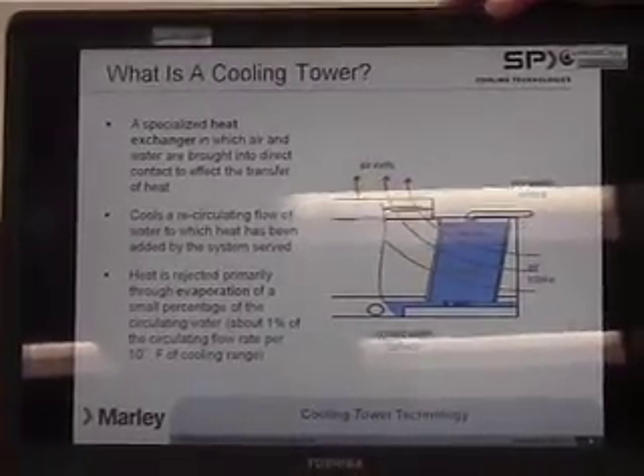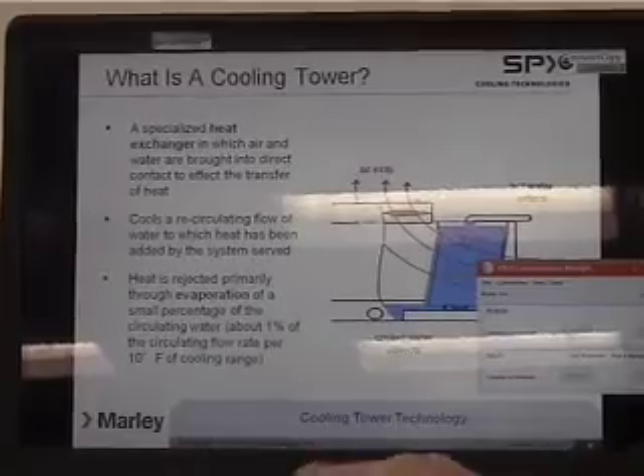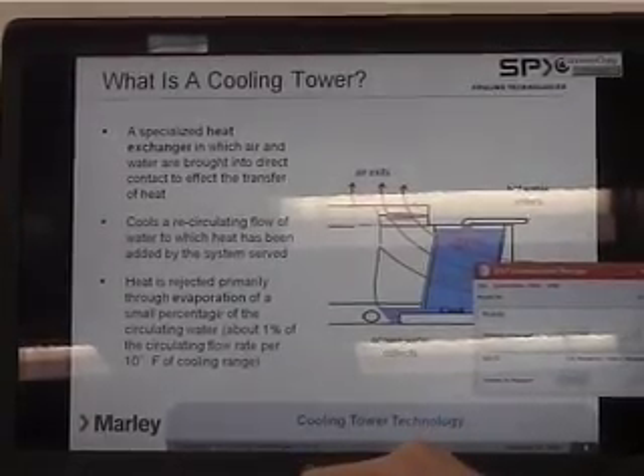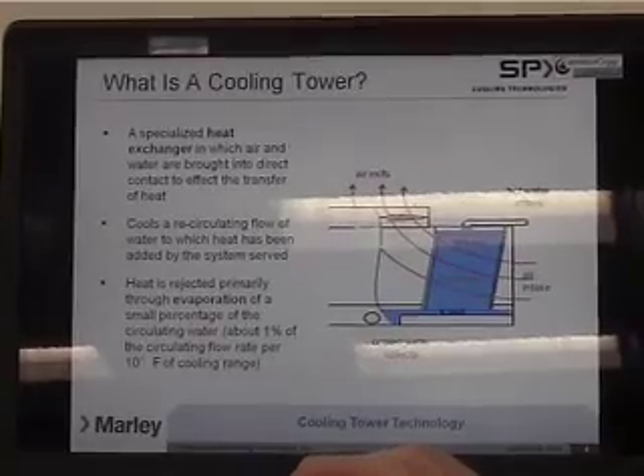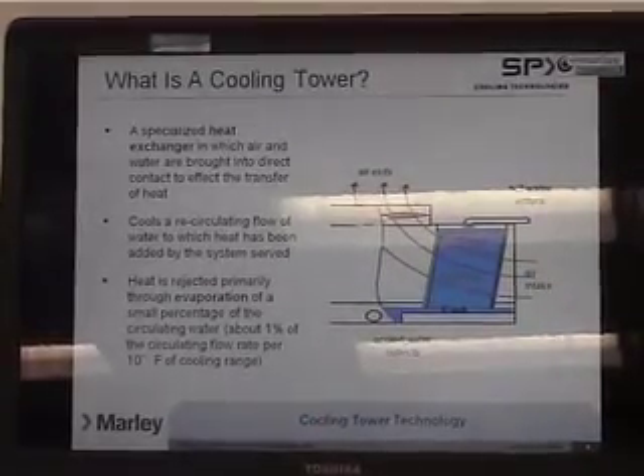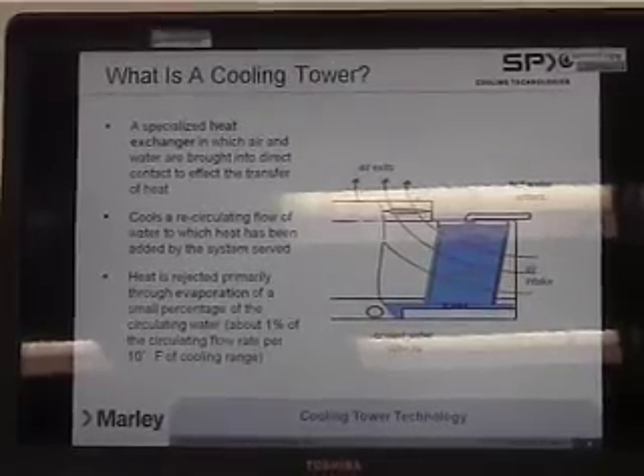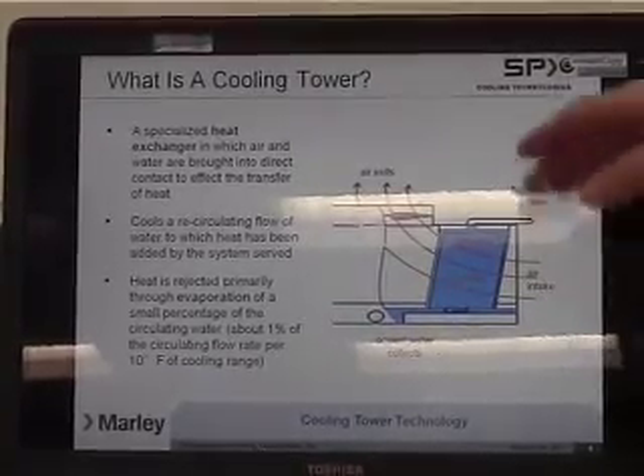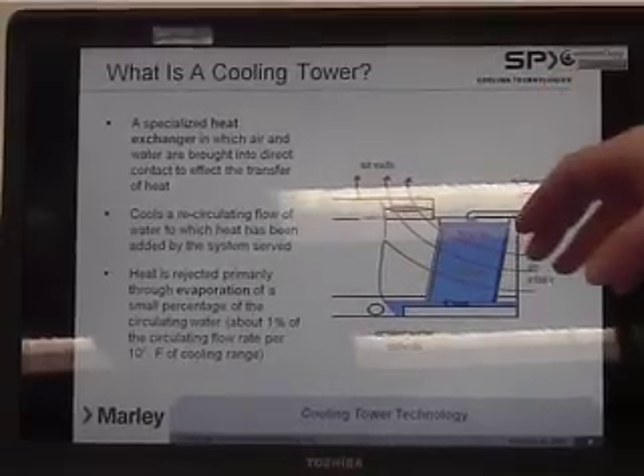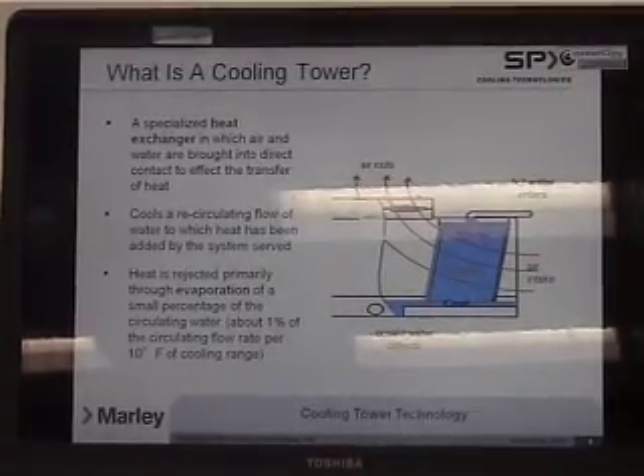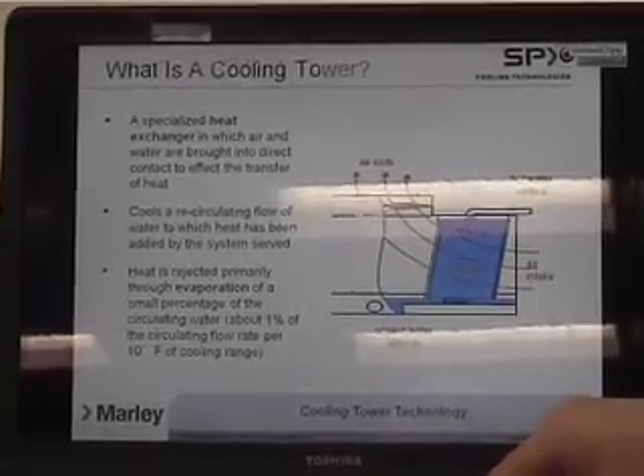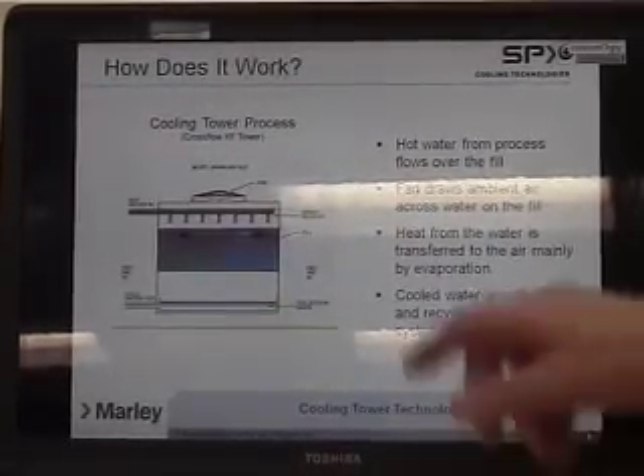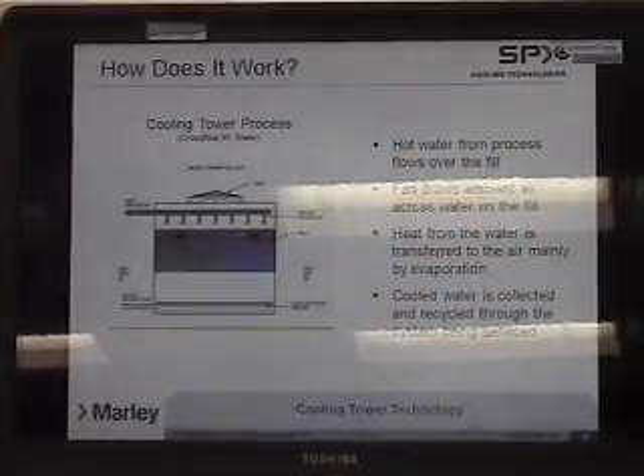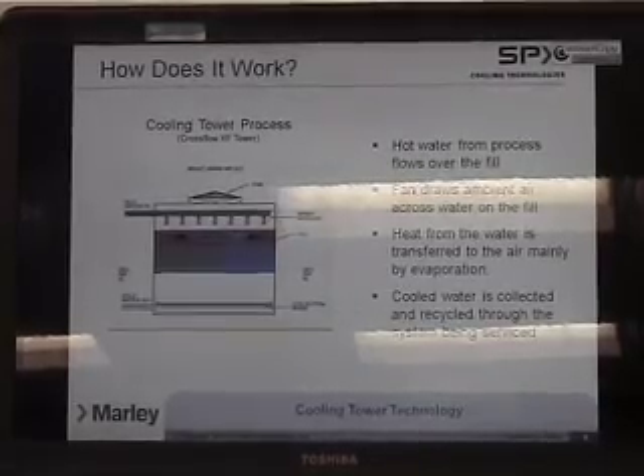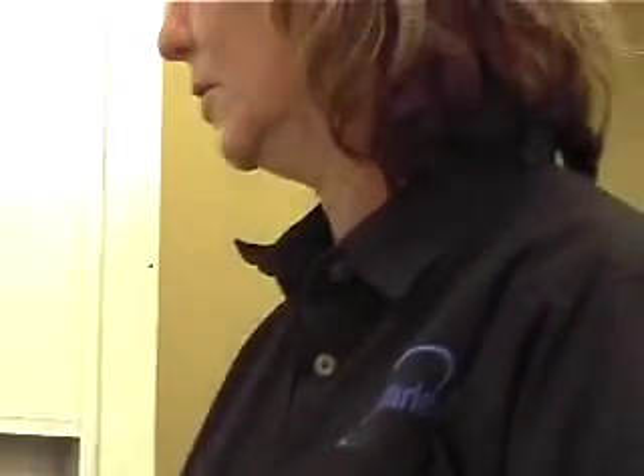The cooling tower is just designed to cool water. It cools by evaporation. The condenser water picks up the heat load, brings it to the cooling tower. The cooling tower moves the heat load from the water into the atmosphere by evaporation. Again, all it's doing is transferring heat around from your condenser water to the cooling tower and then out into the atmosphere.